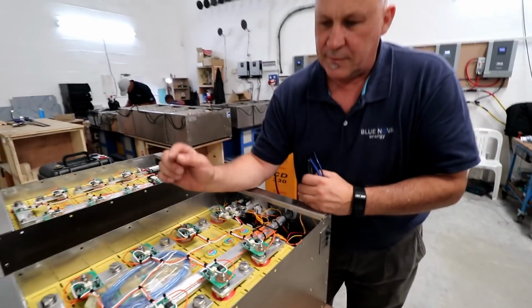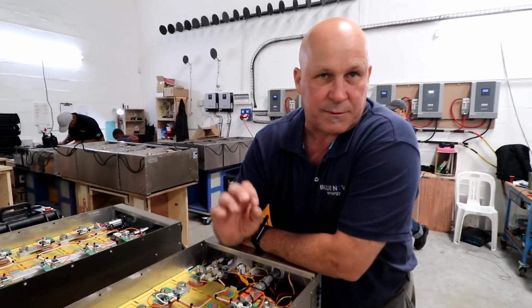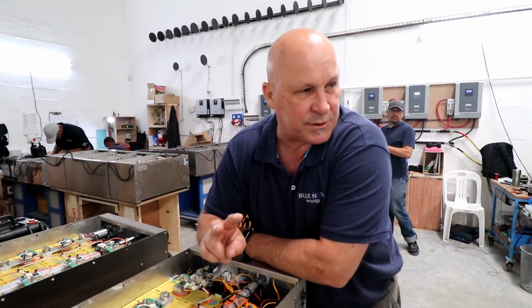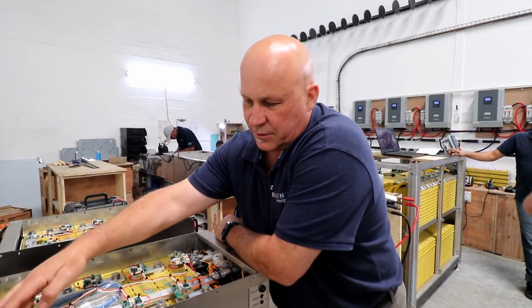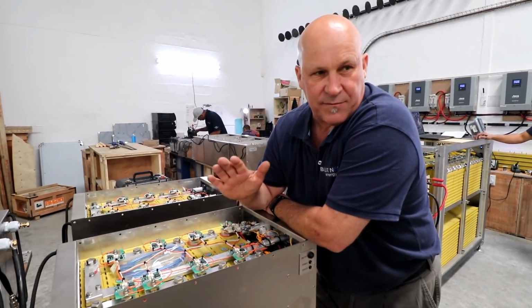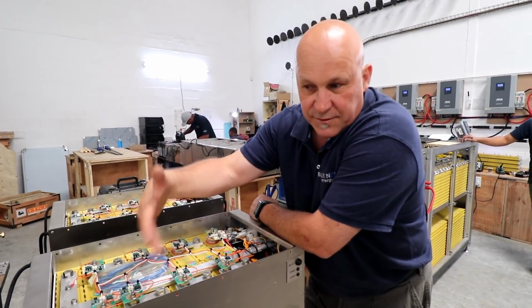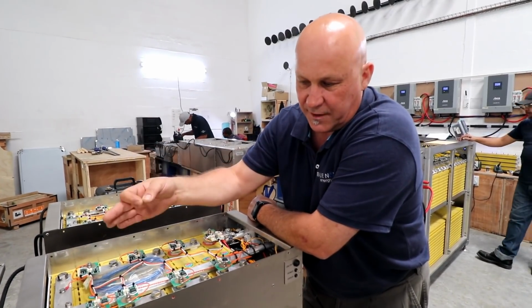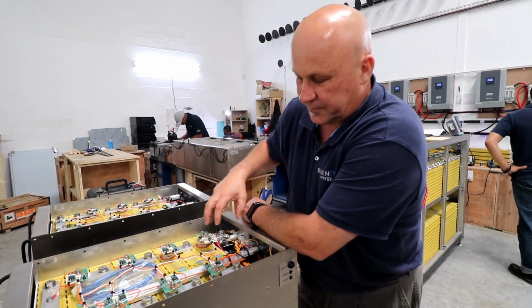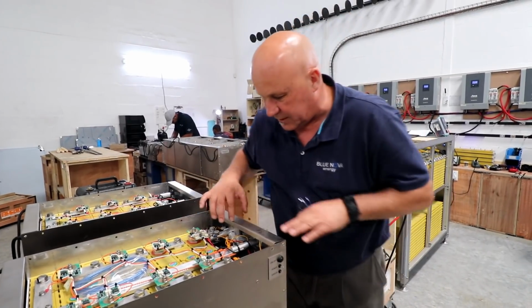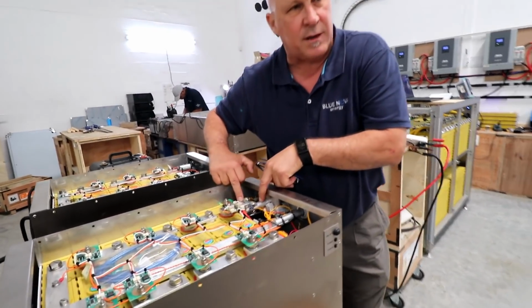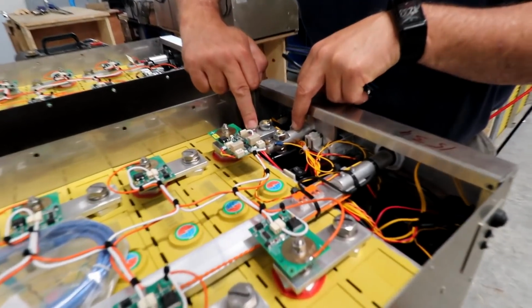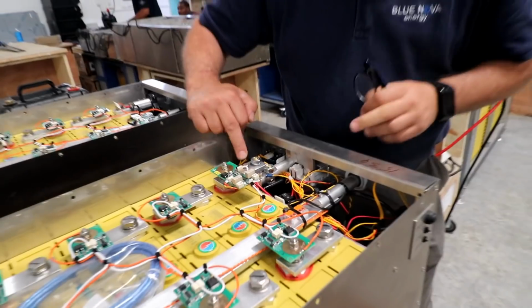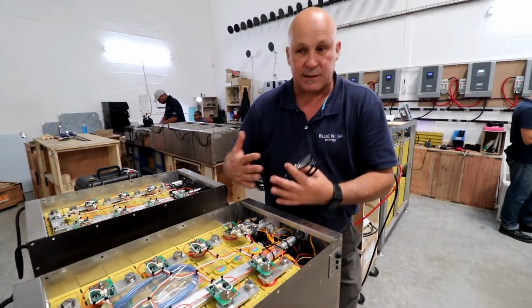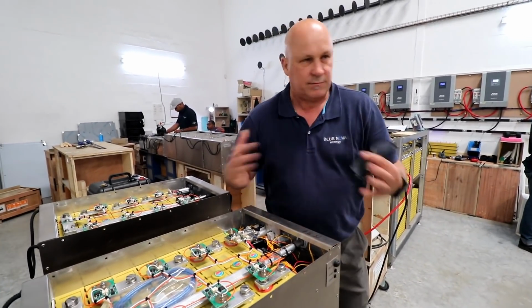So basically, every single cell in a battery has to be monitored, the voltage and the temperature. We monitor the cell voltages with these cell boards up to about 5 millivolts. Typically voltage is 3,500 millivolts, and we measure accurately to 5. We then run our protection circuit. So all the things are measured here. Then on this side, we have a high power impulse relay. So this impulse relay can handle 2,500 amperes. The idea is that if there's any faults, we disconnect the battery from the load instantaneously.